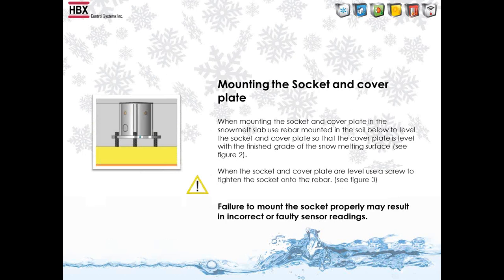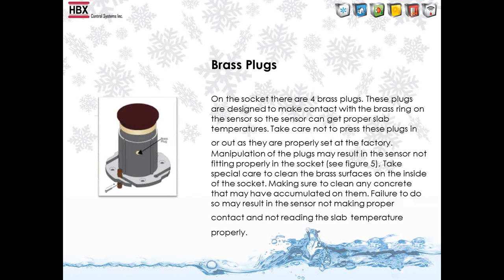When mounting the socket and cover plate in the snowmelt slab, use rebar mounted in the soil below the level of the socket and cover plate so that the cover plate is level with the finish grade of the snow melting surface. On the socket, there are four brass plugs that make contact with the brass ring on the optical sensor to read the slab temperature. Do not manipulate the plugs, as this will affect the proper functioning of the temperature sensor.